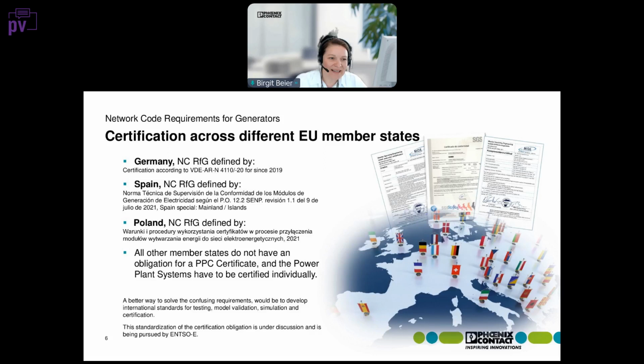All other member states do not have an obligation for a power plant controller certificate, and the power plant systems have to be certified individually. Of course, all power plants have to be certified individually, but in those countries you have more work with certification, testing and model validation. It would be a better way to solve these confusing requirements if we developed an international standard for testing, model validation, simulation, and certification. This standardization of the certification obligations is under discussion now and is being pursued by ENTSO-E. And we believe that in the coming years there will be more certificates, or more need for certificates.